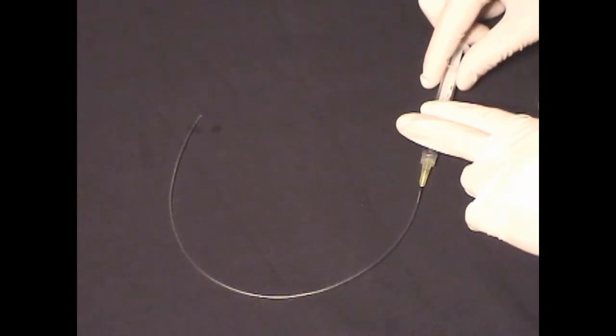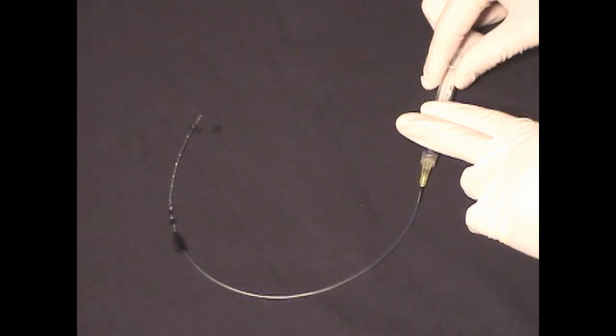Here is a demonstration of liquid distribution. As you can see there are liquid droplets forming at every fenestration. Do not test your tubing this way prior to sterilization, as it is best to keep your patient tubing completely dry for that process.